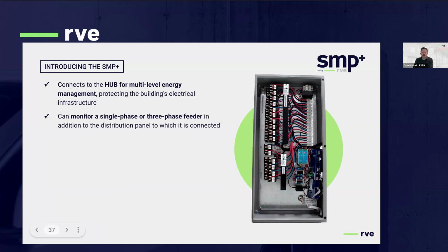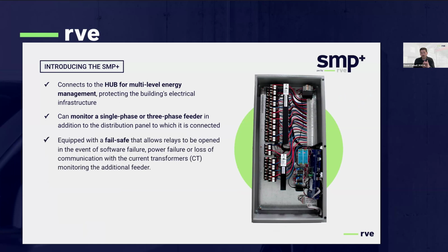In terms of design, it's made for large-scale deployment. We have buildings where SMPs will eventually power hundreds of cars. To protect the infrastructure, we've included features that enable multi-level energy management, which is really the only way to comply with Rule 8-106-11. It's to have CTs that monitor both the main service and the sub-feeders, but that also have relays with fail-safe features, so that if there's ever a miscommunication along the way, we can stop the charging and assess the trouble if there is one.